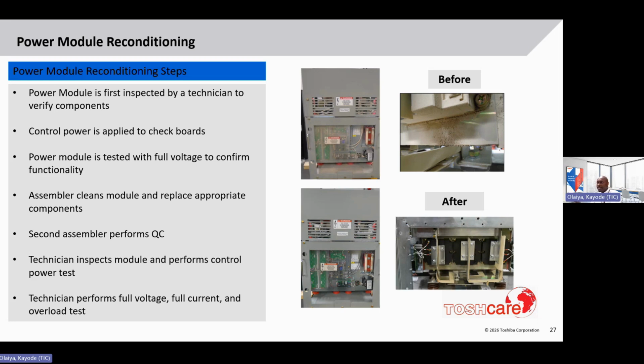So here is to give you a picture of what happens to a module when it comes to the Toshiba repair shop. First is that the module is inspected by a technician to verify that it is in good working condition. Remember that the reconditioning service is preventive, which is different from a repair. So the goal is to make sure that the components that are now being replaced are still functional and will last. And so we apply control power to verify the board signals after inspecting the components. And then the module is tested with full voltage to make sure that it is operational.